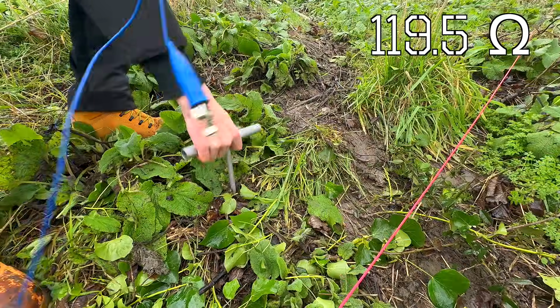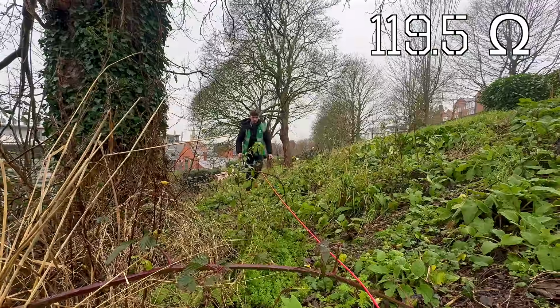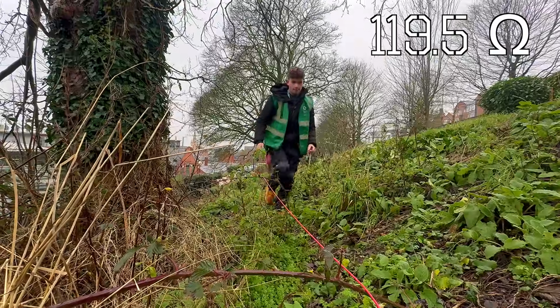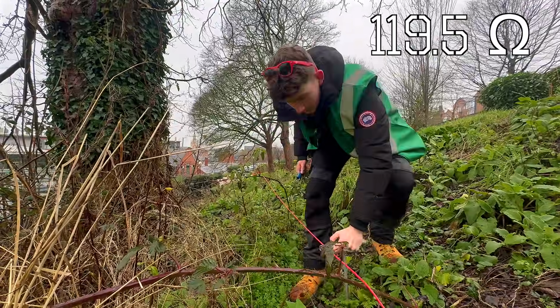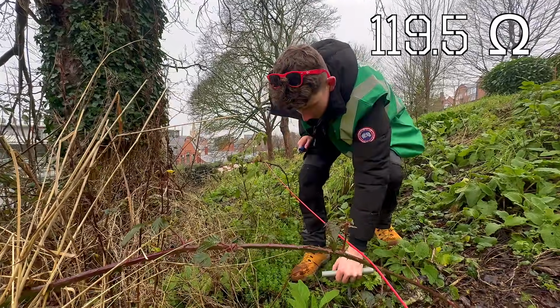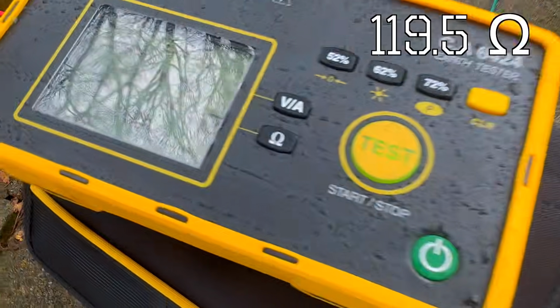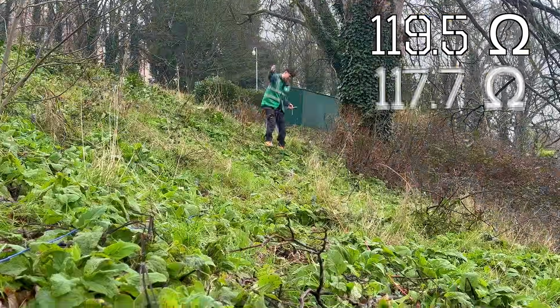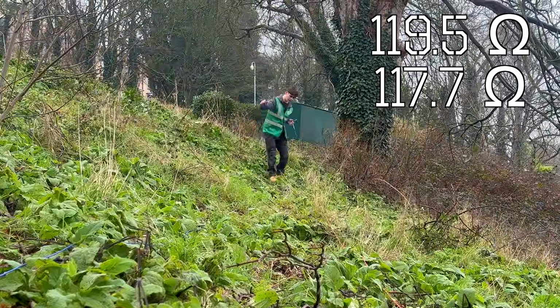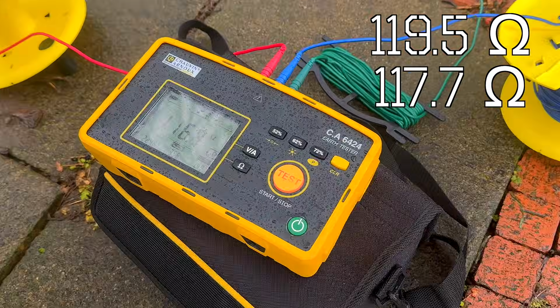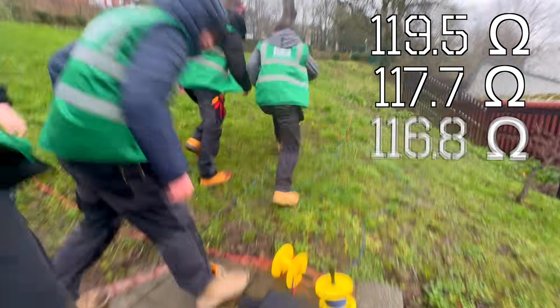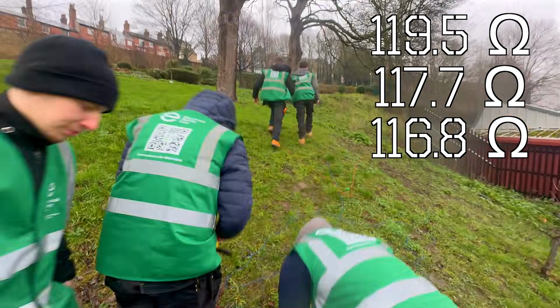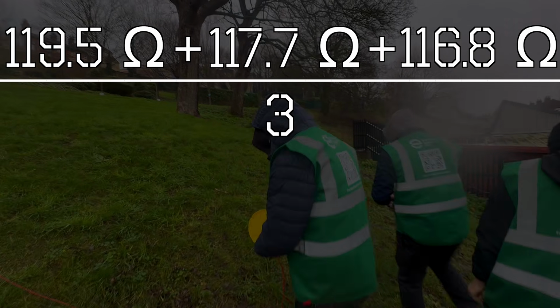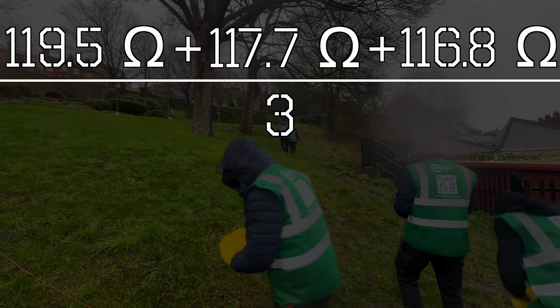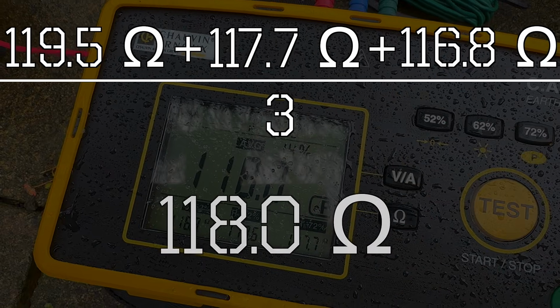Next we go to 72%. This moves the potential probe 10% closer to the current probe, a distance of 3.6 meters and a total of 26 meters from the electrode under test. And we take that measurement. Finally, we go to 52%. This is around 18 meters from the electrode under test and we take the final reading. So now we have all 3 readings, we can calculate the mean average. To do this, we add them together and divide by the number of values we have. In this case, 3. This gave us a mean average of 118 ohms.